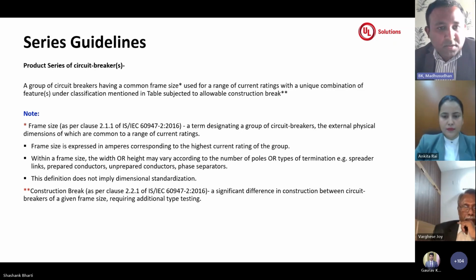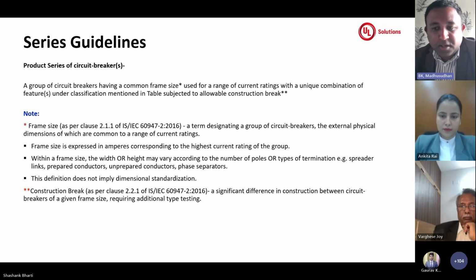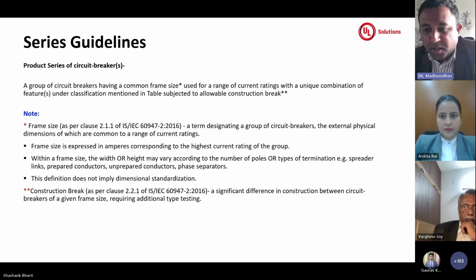To start with, for the series guidelines, first of all, the manufacturers have to confirm the frame sizes with respect to that particular series. Frame size basically consists of the maximum size within the breaker range. For example, you may have a breaker range from 6 to 63 ampere, and another frame size from 80 to 125 ampere. Based on the physical dimensions and the internal current carrying parts, you have to declare those frame sizes in detail, so that the samples will be selected according to the requirements from the series guidelines.